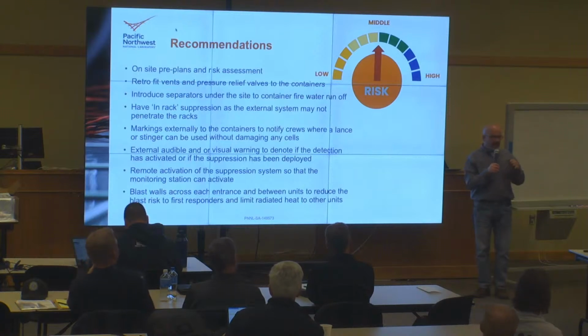But even if you have thermal runaway in one rack and the sprinkler opens up, now you have five gallons a minute flowing out that module down onto all the other modules, and where is it? So water is a tough one.